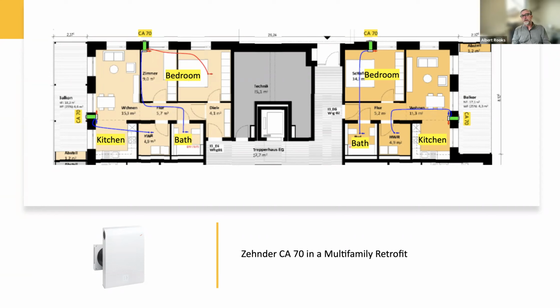We can look at adding a humidity sensor so that if we're placed in a bathroom, or it's got a return duct hooked up to a bathroom, someone showers, humidity goes up, it'll see the humidity and then go into a boost mode. So it's cruising at the normal rate all the time, and then when humidity goes up it goes into boost mode. There's also CO2 sensors: if we place it in that bedroom, or in a location where the exhaust stream sees CO2, it'll send it into a boost mode. There's another device that we're going to look at from FreshR, which takes that a step further. A little more money, a little more options, super interesting. So here's one way that we can deploy into that building.